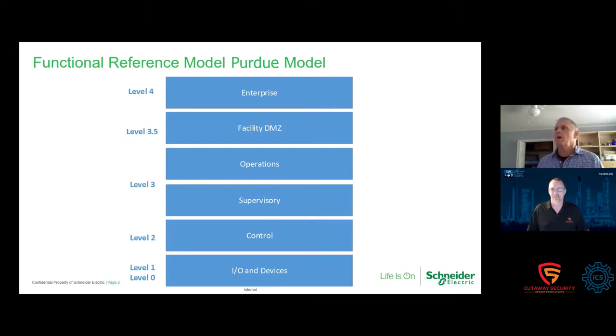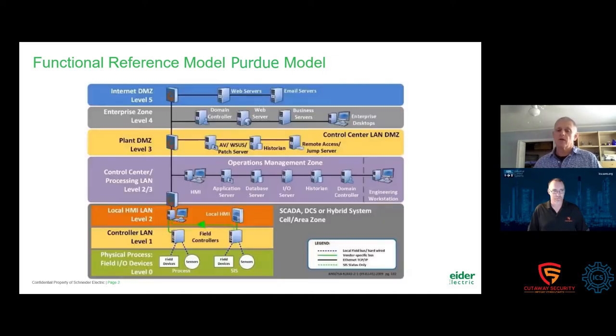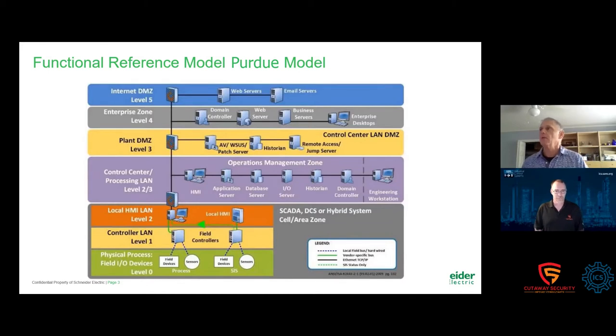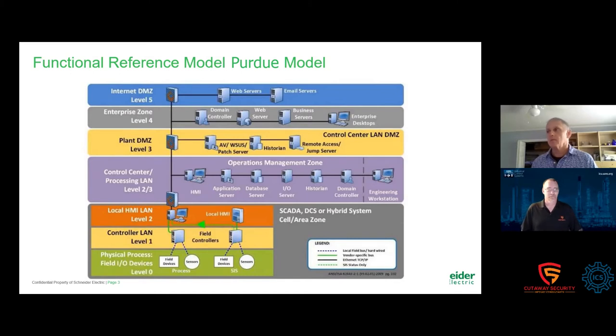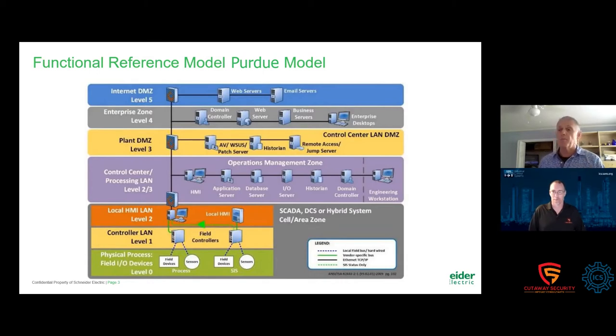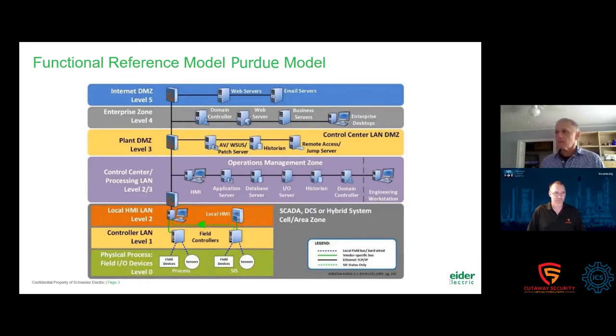When you start seeing things like this — here's an example of a Purdue with firewalls placed between the functional levels — I think you should have firewalls, especially around safety systems. Including a data diode, or as my friends at Waterfall call it a unidirectional gateway, would probably be the best thing to put in front of a safety system. But my experience is that people conceive this as a security reference architecture, and it's not — it's pure OT functionality.